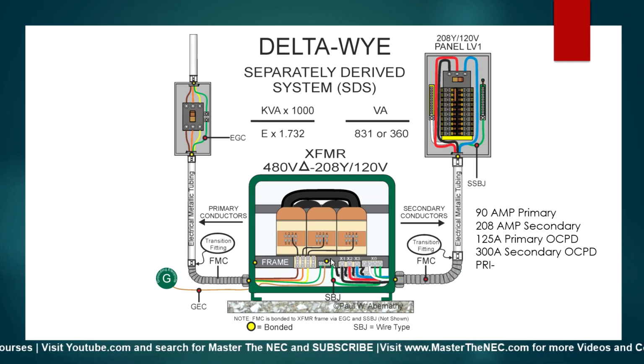All right, now let's go on and size the system bonding jumper. Let's see how we size that, okay? And the system bonding jumper, because it's a wire type, is allowed to connect the equipment grounding conductors as well as the grounding electrode conductor over to the XO. That's under the exceptions that allow it to do that.